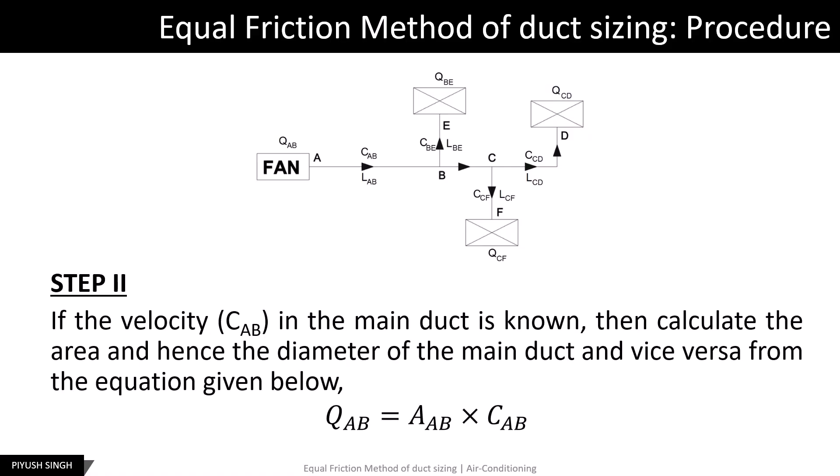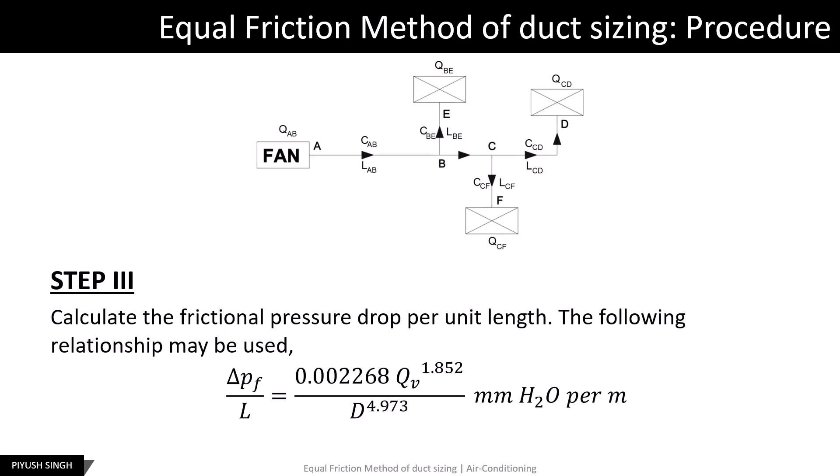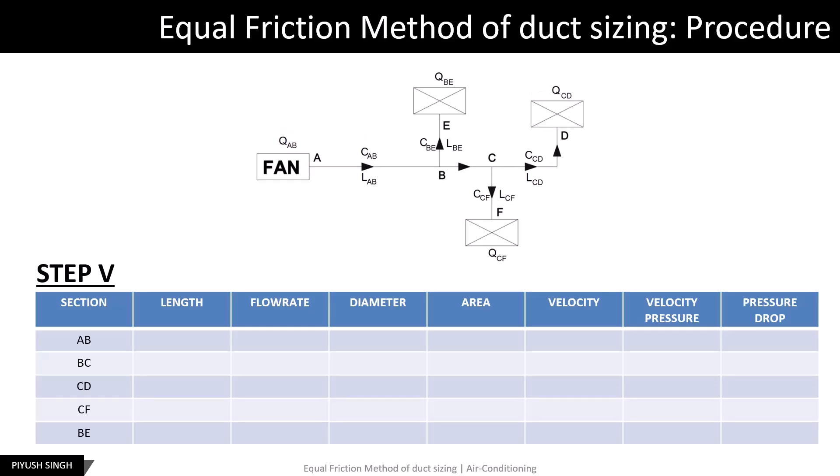The volumetric flow rate is equal to the product of the cross-sectional area of the duct and the flow velocity. If we have the velocity in the main duct, we can calculate the cross-sectional area and hence its diameter. Alternatively, if provided with the cross-sectional area or diameter, we can calculate the velocity. In step 3, we calculate the frictional pressure drop per unit length using the empirical relationship. In step 5, data is compiled in a table showing duct length, flow rate, diameter, area, velocity, velocity pressure, and frictional pressure drop.